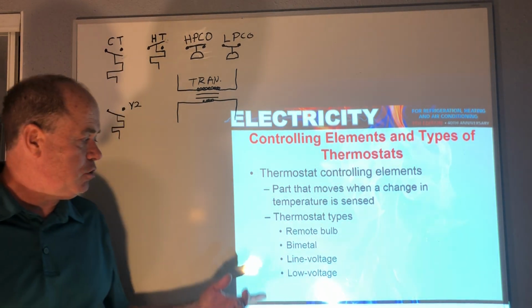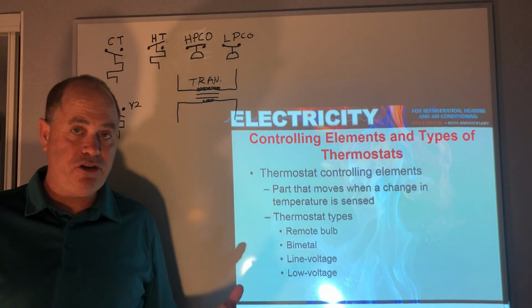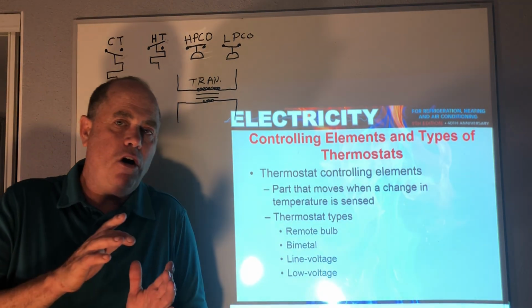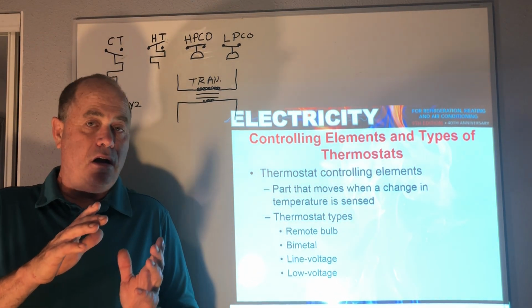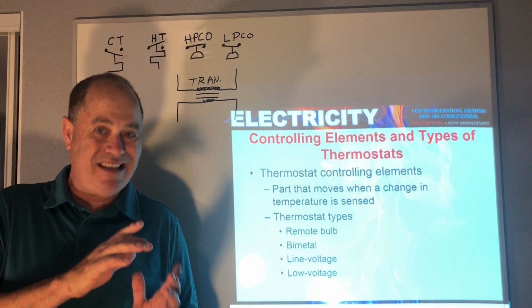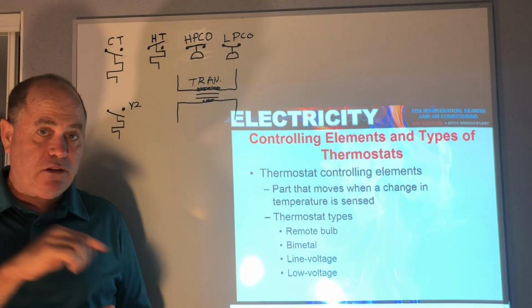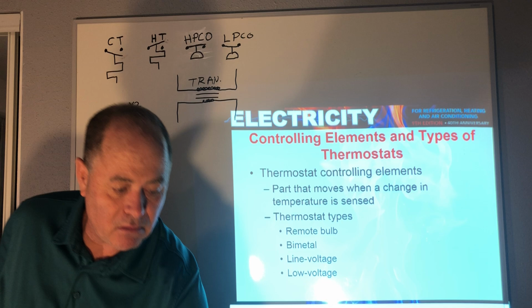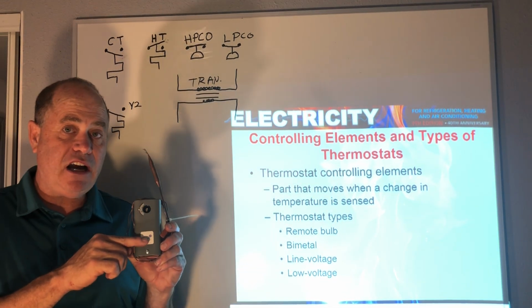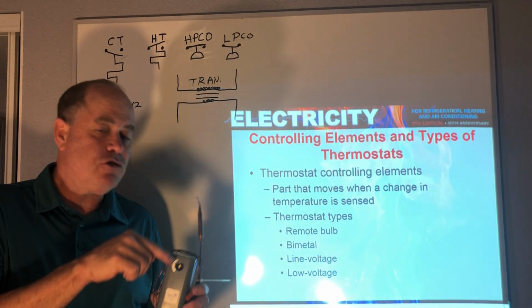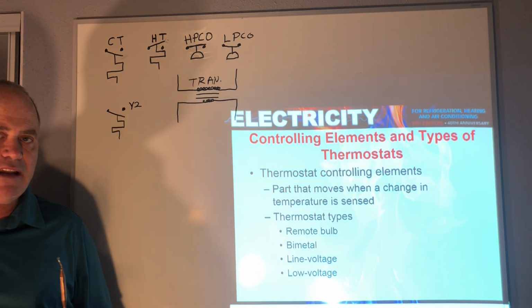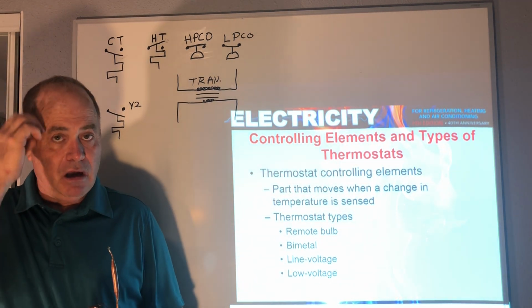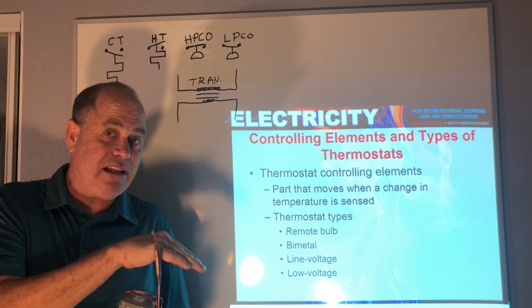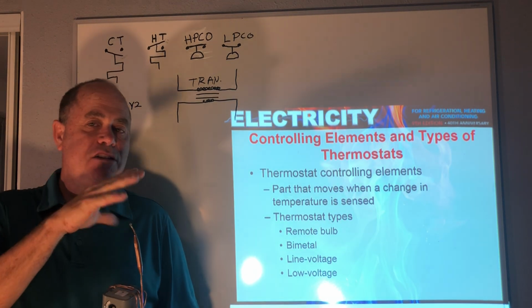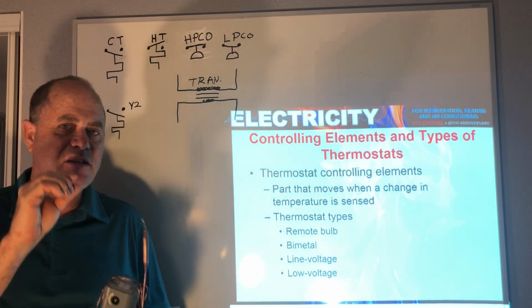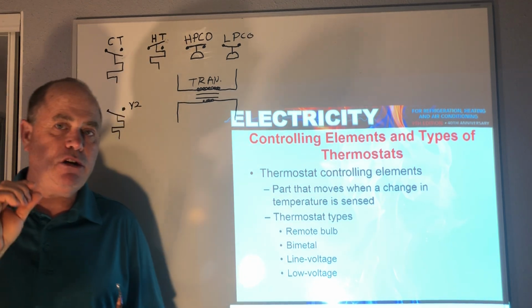It's a little counterintuitive. The line voltage or high voltage thermostat is for small air conditioning or refrigeration systems. We have a direct thermostat, something that will let the line voltage and higher amperage through it, and this directly line voltage thermostat lets the electricity go through it to directly turn on the compressor. And these are for small systems because the contacts of a thermostat can handle that 3 or 4 amps.